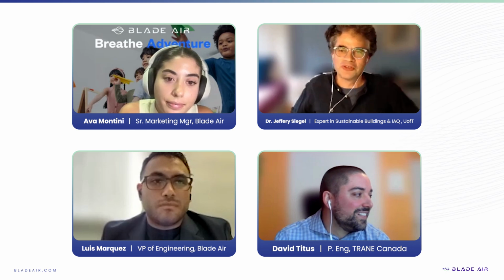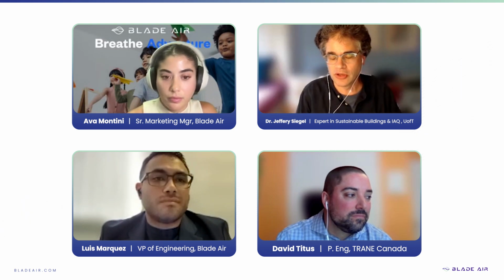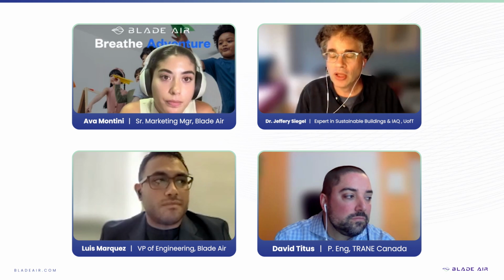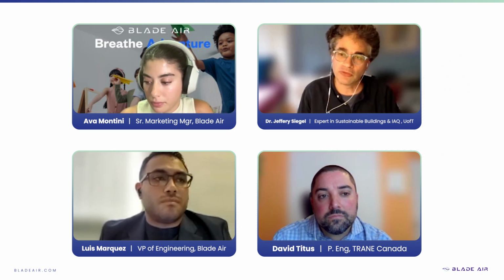Oh boy, there is a ton of science, and I could talk all day about this, but the fundamental issue is, and this is a different issue from polarized media, just so everyone's on the same page: many filters used in schools and in the marketplace in general have a charge added to them in the factory to enhance their removal. This is a great idea and it works quite well, but it can decline as the filter ages. And so the idea of people using the MERV A rating is that you can be relatively convinced that your filter's performance will continue for the long term.